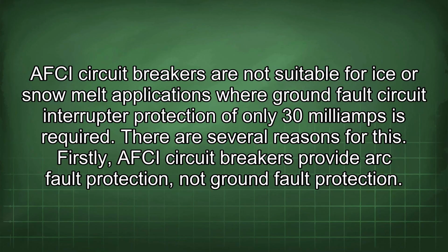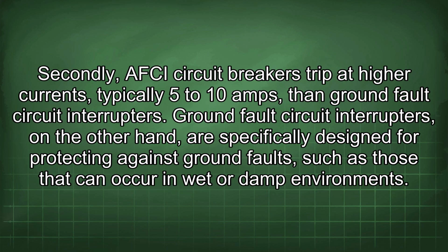AFCI circuit breakers are not suitable for ice or snowmelt applications where ground fault circuit interrupter protection of only 30 mA is required. There are several reasons for this. Firstly, AFCI circuit breakers provide arc fault protection, not ground fault protection. Secondly, AFCI circuit breakers trip at higher currents, typically 5 to 10 amps, than ground fault circuit interrupters.